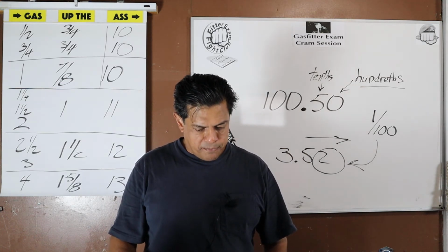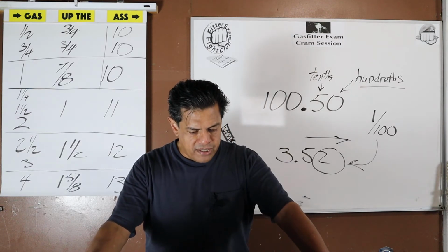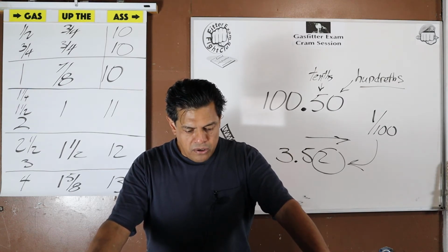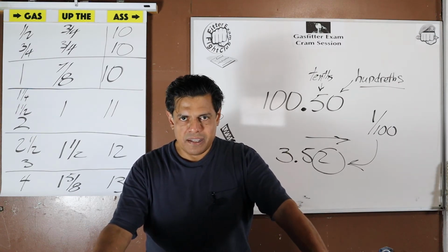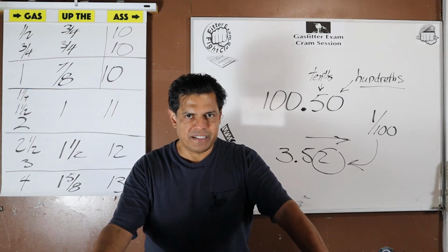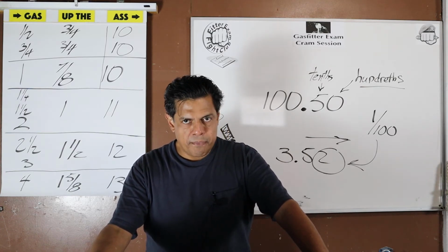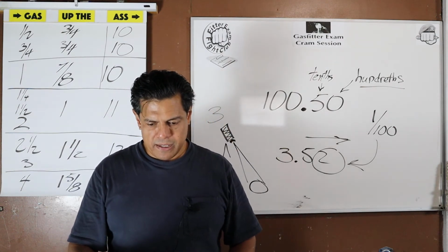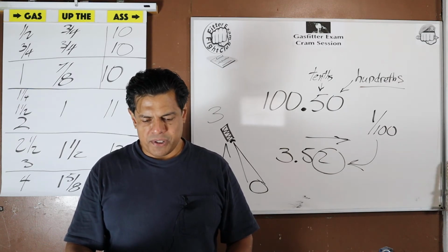Unless incorporated as part of gas burning appliance, a sediment trap shall be installed downstream of the appliance shutoff valve. We're going to remember this as anything that has to do with the appliance is going to be downstream of the appliance shutoff valve. The shutoff valve is to completely isolate that appliance and everything pertaining to it. So, that sediment trap is for the appliance. It's going to be downstream of the appliance valve. Okay. Page 25, question 11.